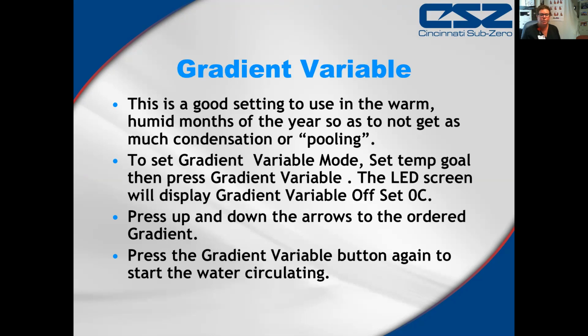So to do that, all you do is hit the gradient variable button. The screen will light up, and then you press the up or down arrows to get the number that you're looking for. I would suggest that if you are using a gradient 10 and you're not able to achieve that, I would go to gradient variable and try 15 degrees. And if 15 didn't work, then I would try 20. So I wouldn't go directly to 20 right away, because again, the greater the difference between the water temperature and the patient, the greater chance there is for overshoot. So I would try 15 and then go towards 20.